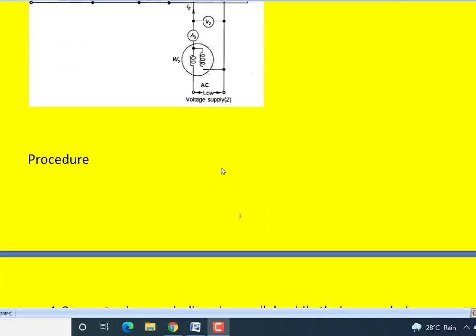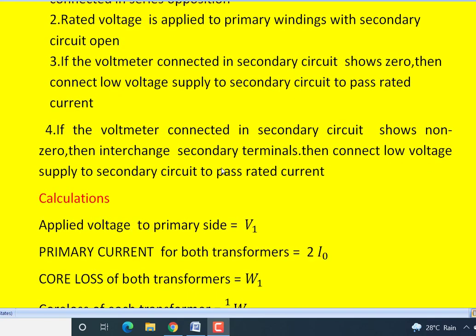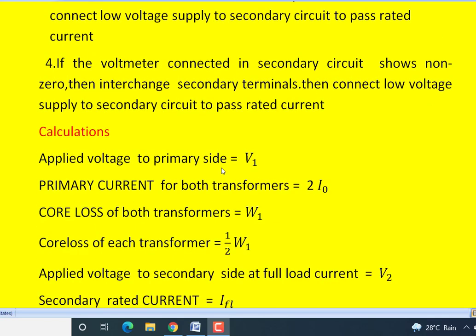So then, going to the calculations, the applied voltage to the primary side, as we have seen, is V1, and the primary current for both the transformers put together is 2I0. For individual transformers, the no load current or primary current will become I0. And the core loss of both the transformers is measured as W1. The core loss of each transformer is half into W1, meaning W1 by 2.